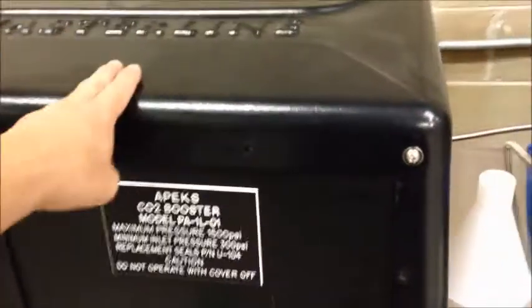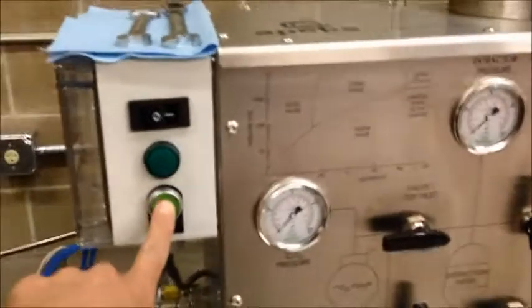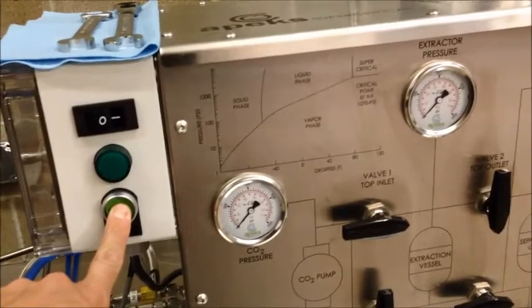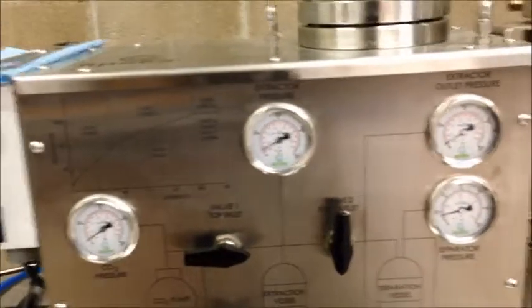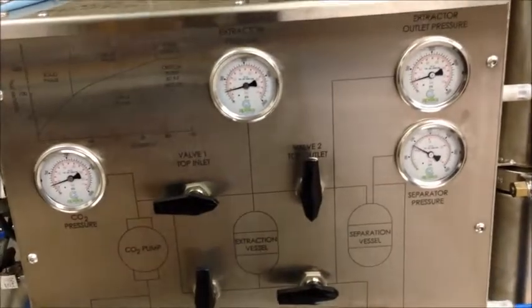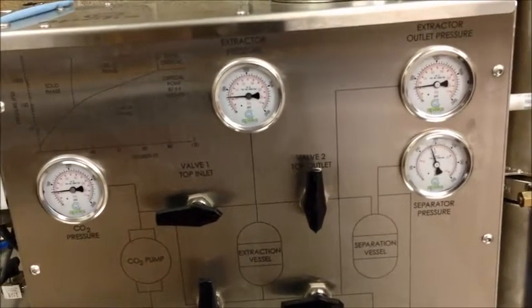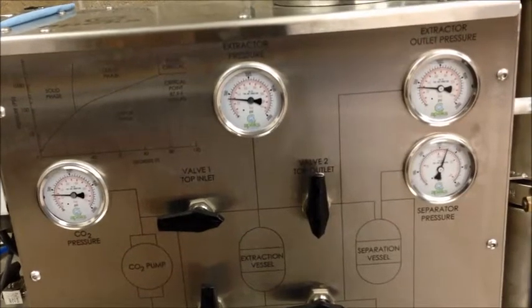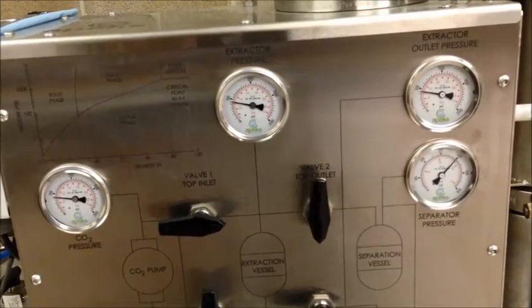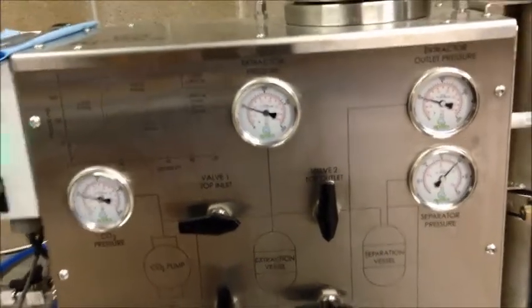Make sure that your system's plugged in and your breaker is on. Make sure your pump is plugged in. Come over here. It hasn't been reset since the last time, so I'm just going to push the start button to reset it. System ready, hold start for 3 seconds to begin. So I've got everything closed, my chiller's on, and hold 3 seconds. So what's happening now, the system's filling up. Once it reaches a certain pressure, the pump will kick on. Right there, the pump just kicked on.